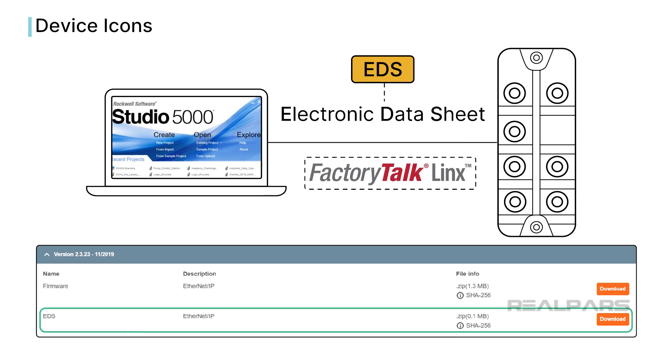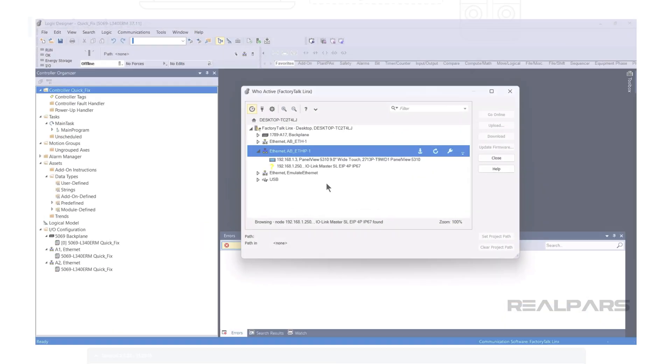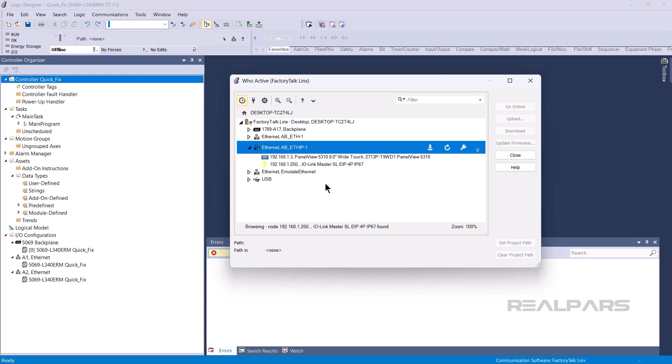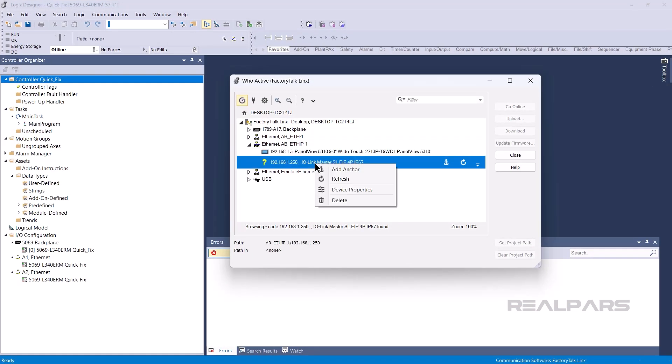EDS files for devices can be found on the manufacturer's website. And very often you can upload the EDS directly from a device by right-clicking and selecting Upload EDS. Once the EDS for a device is installed, the yellow question mark will go away.